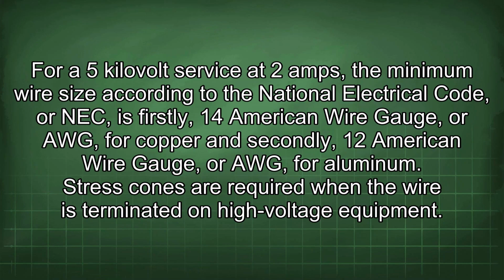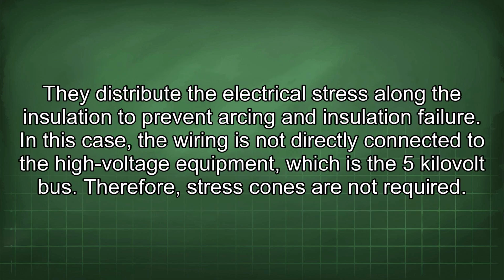For a 5 kV service at 2 amps, the minimum wire size according to the National Electrical Code, or NEC, is firstly 14 American wire gauge, or AWG, for copper, and secondly 12 American wire gauge, or AWG, for aluminum. Stress cones are required when the wire is terminated on high voltage equipment. They distribute the electrical stress along the insulation to prevent arcing and insulation failure.